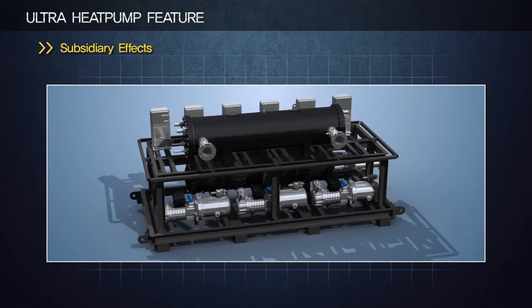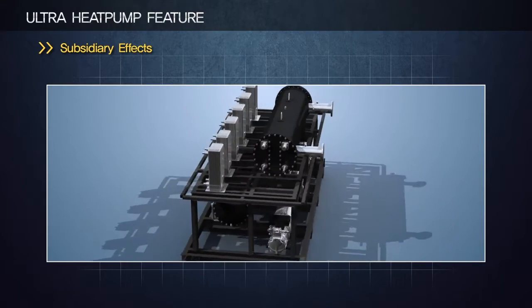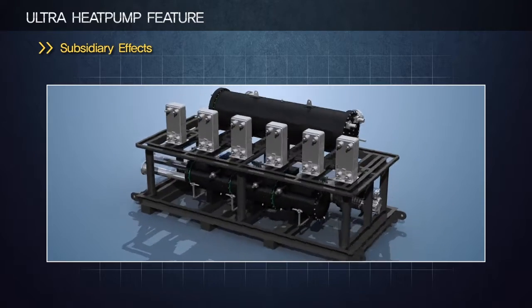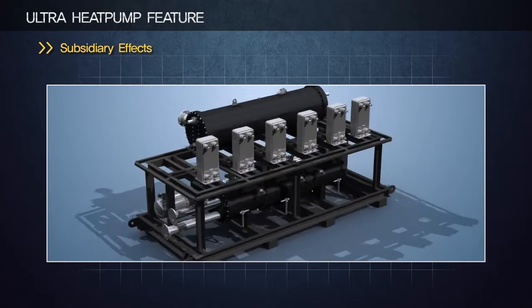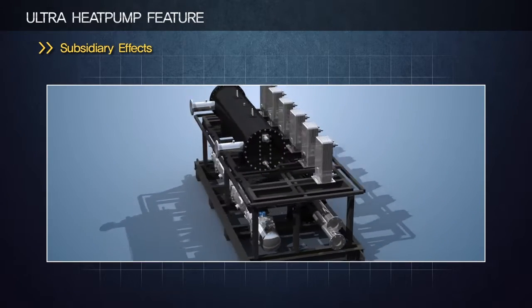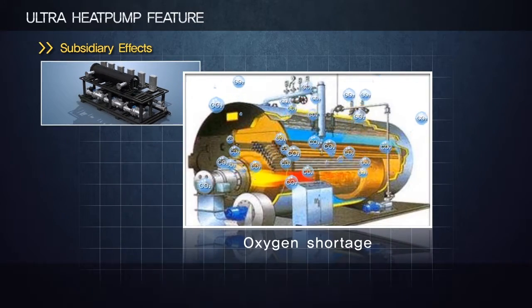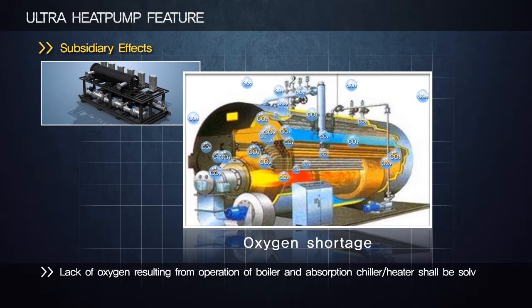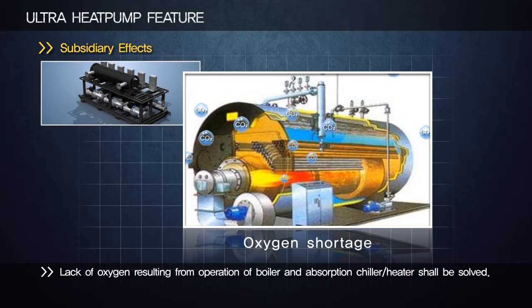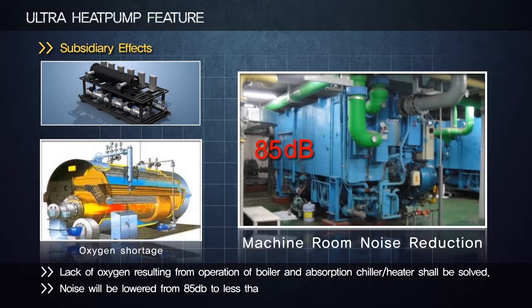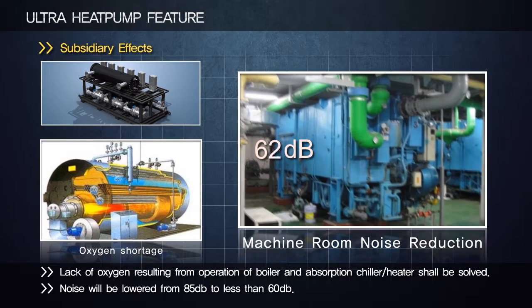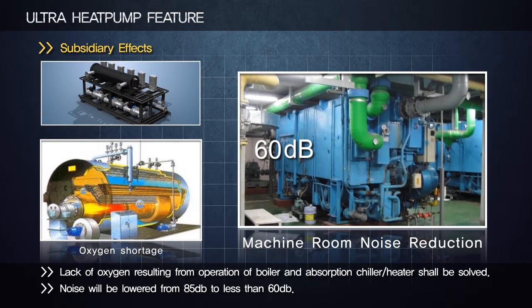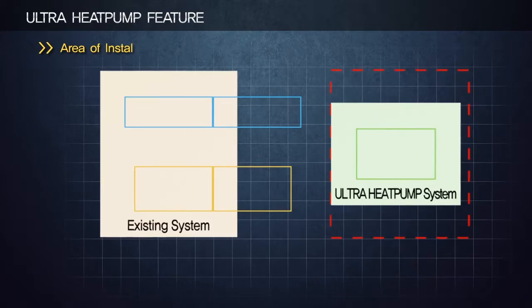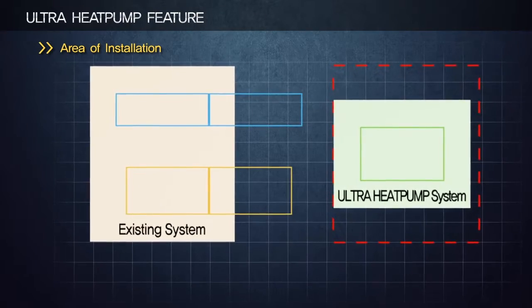Using ultra heat pump will remarkably reduce energy costs and solve the carbon dioxide emission issue at the same time. Furthermore, many subsidiary effects are accompanied. Lack of oxygen resulting from operation of the boiler and absorption chiller heater will be solved. Noise will be lowered from 85 decibels to less than 60 decibels. Installation size will be reduced by half.